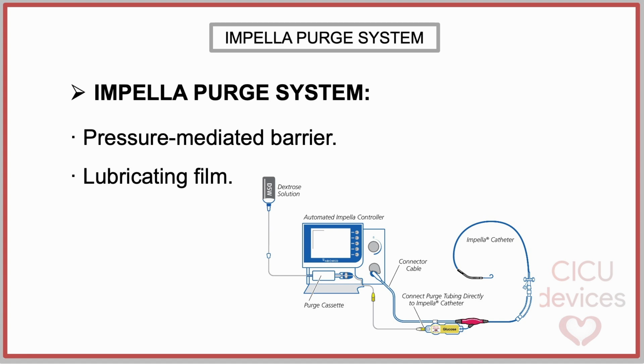Functionally, the Impella purge system operates as a pressurized fluid circuit that continuously delivers a dextrose-based solution through dedicated tubing and control hardware. By maintaining a controlled counterflow pressure at the motor housing, the system minimizes blood exposure to internal components, reducing the risk of device-related thrombosis and hemolysis while stable left ventricular support is provided.